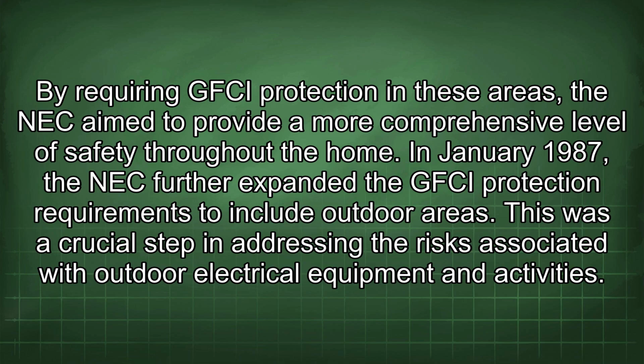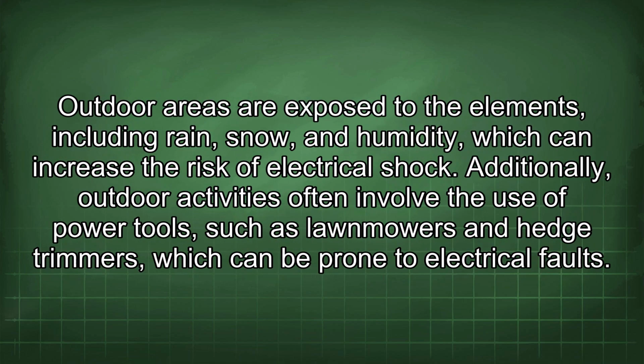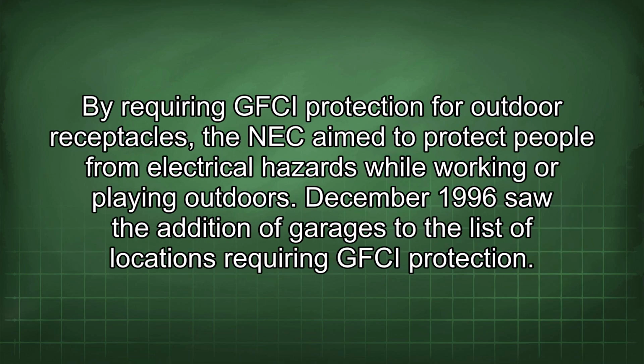In January 1987, the NEC further expanded the GFCI protection requirements to include outdoor areas. This was a crucial step in addressing the risks associated with outdoor electrical equipment and activities. Outdoor areas are exposed to the elements, including rain, snow, and humidity, which can increase the risk of electrical shock. Additionally, outdoor activities often involve the use of power tools, such as lawnmowers and hedge trimmers, which can be prone to electrical faults. By requiring GFCI protection for outdoor receptacles, the NEC aimed to protect people from electrical hazards while working or playing outdoors.